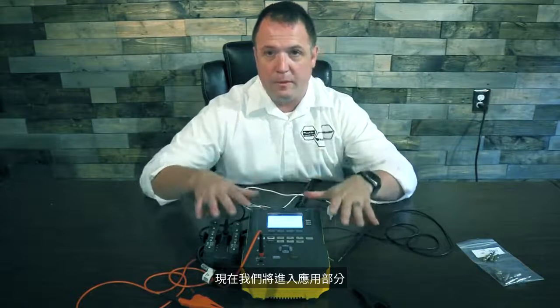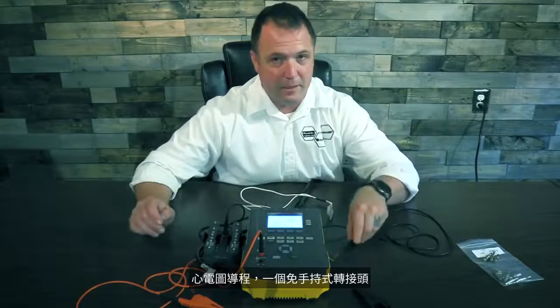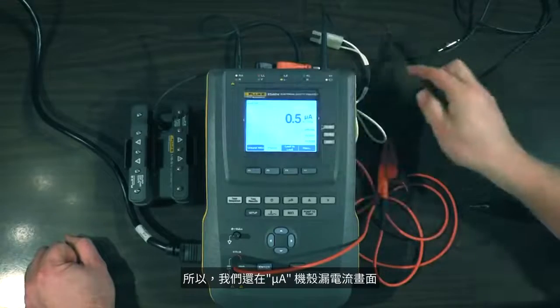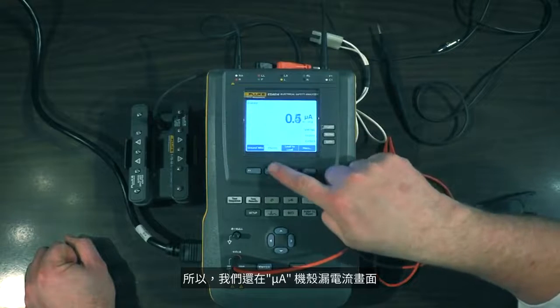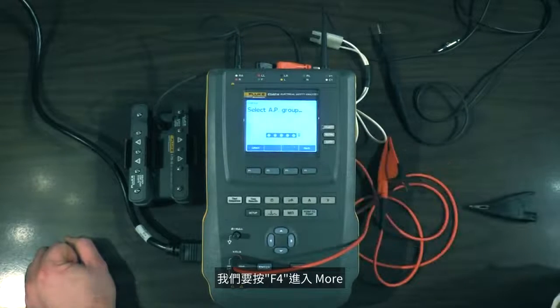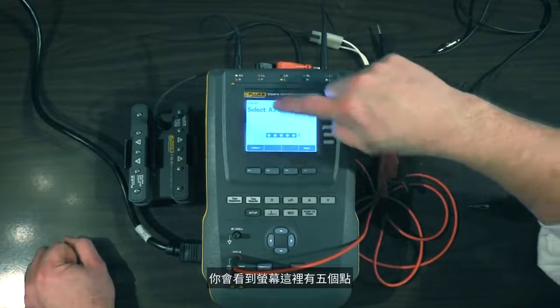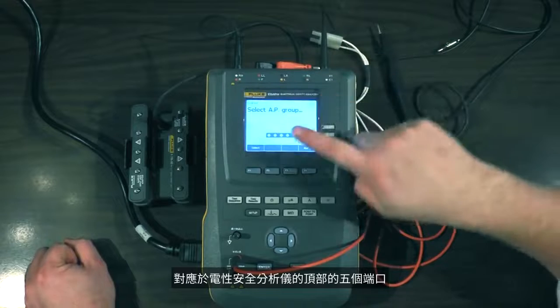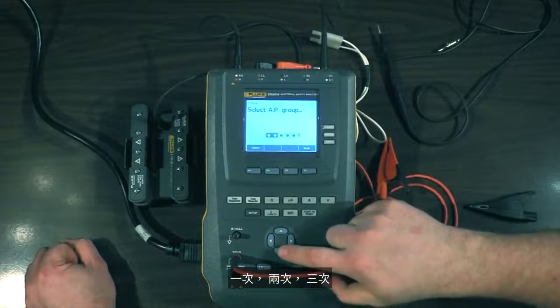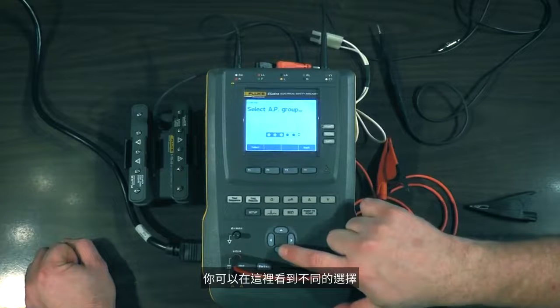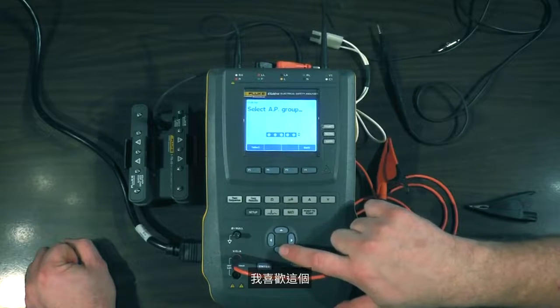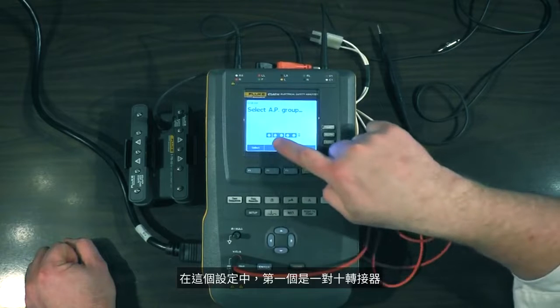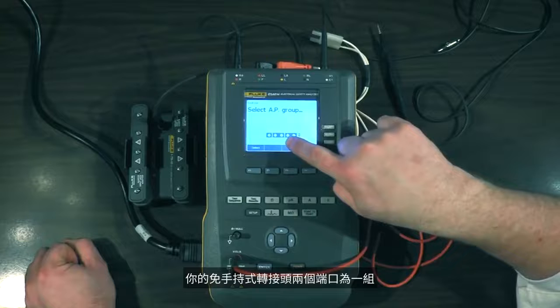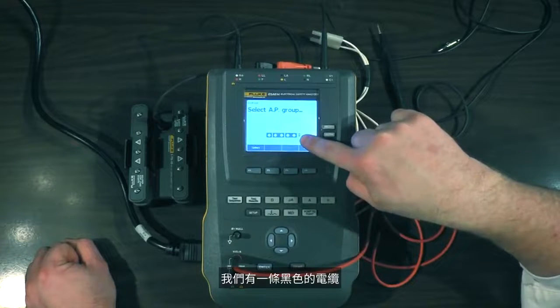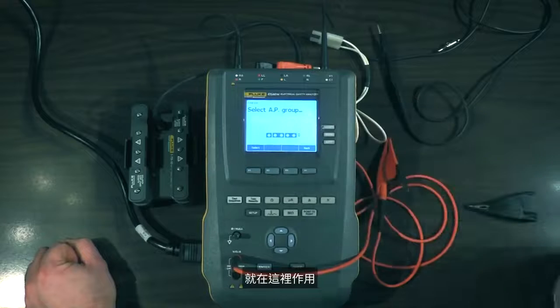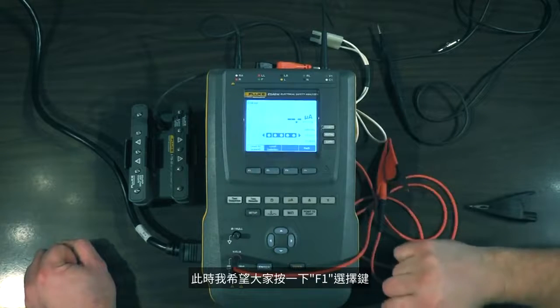Now we're going to get into the applied parts, the ECG leads, the hands-free adapter, and our mystery cable here. So we're still on the µA, the leakage screen, and we're going to go over here to More, F4. You'll see that this black box with the 5 white dots corresponds to the 5 ports across the top of the safety analyzer. We're going to hit the down arrow once, twice, 3 times, and you'll see different selections that you can have here, and I like this one. In this setup, the 1 to 10 adapter is by itself, and then your hands-free adapter is barred together, and these last 2 ports, which we have the one single black cable run out of, is over here by itself. That's the one I want, so I'm going to push select, and now our leakages.